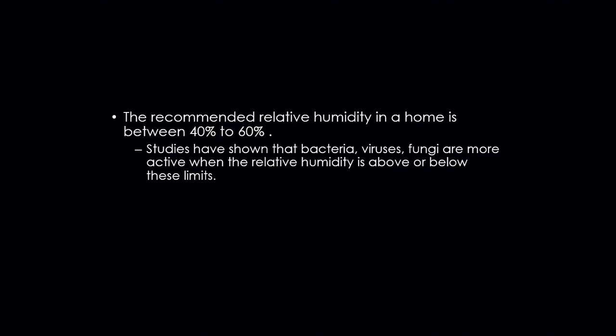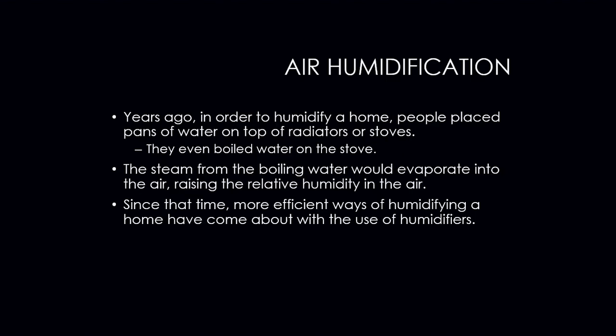Now, it is recommended in HVAC to have a relative humidity in a home of somewhere between 40 and 60%. The reason we have it between 40 and 60% is because studies have shown that bacteria, viruses, fungi, mold, and all that other stuff are better controlled when within those ranges. Does it 100% eliminate the possibility of it? No. But between those ranges, we are able to control and have a better handle on the moisture content within the space.